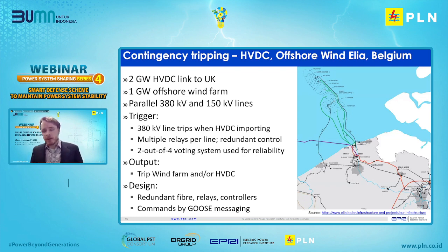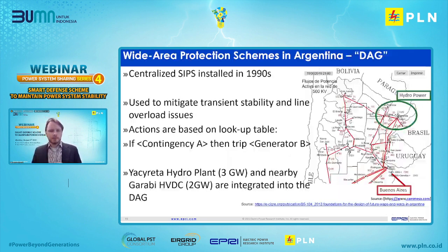They have a very resilient system. So they have redundant control, and they have multiple relays on each line. And they use a 2 out of 4 voting system, so at least 2 relays must recognize the overload for anything to happen. And based on the overloading, either the wind farm is tripped or the HVDC operating point is run back. It's designed using redundant fiber links, redundant relays, redundant controllers, and the commands are all sent by GOOSE messaging. Moving to the next example.